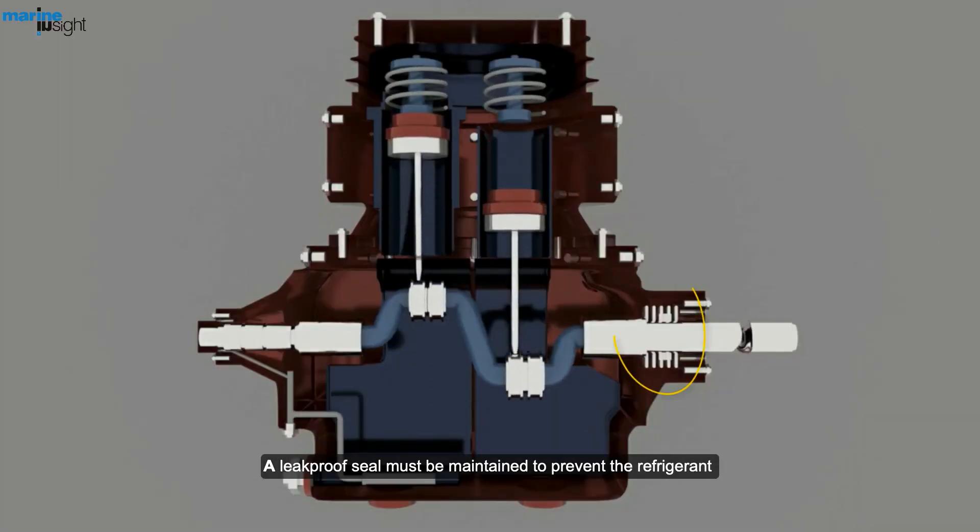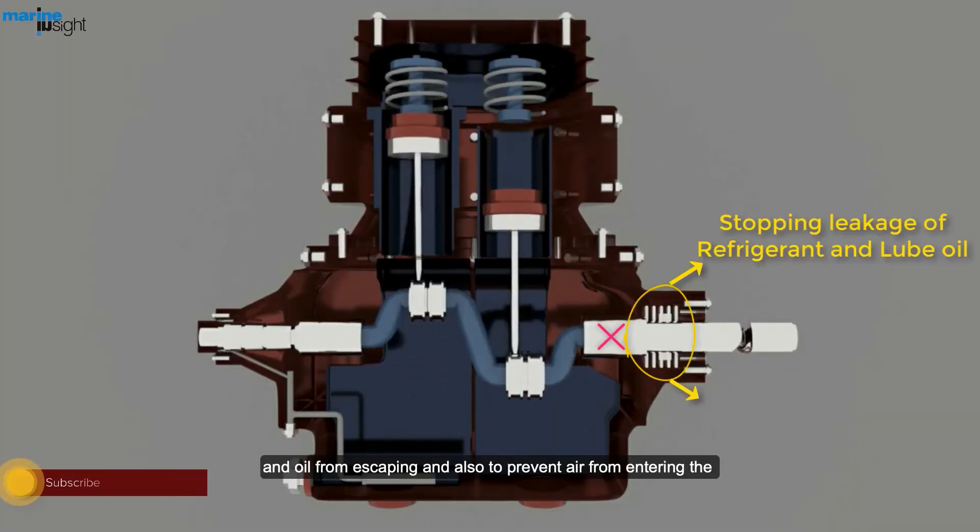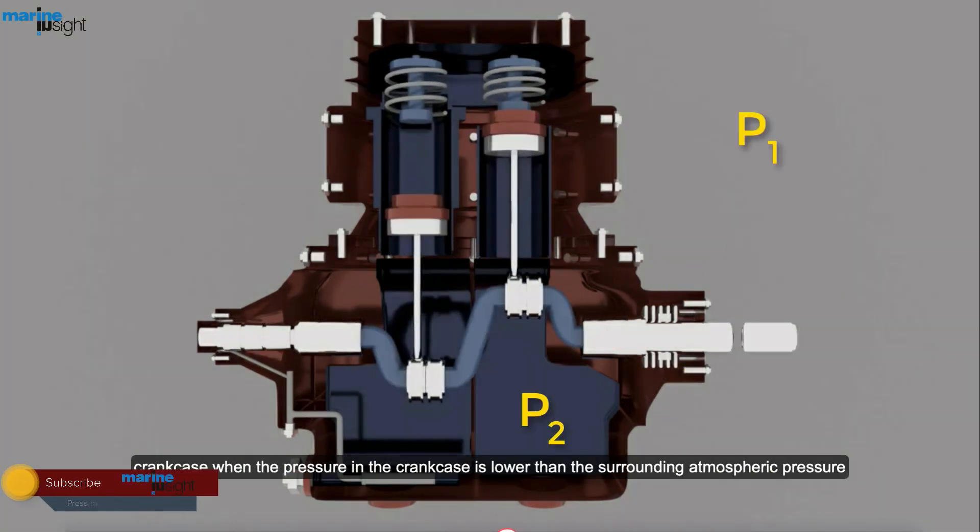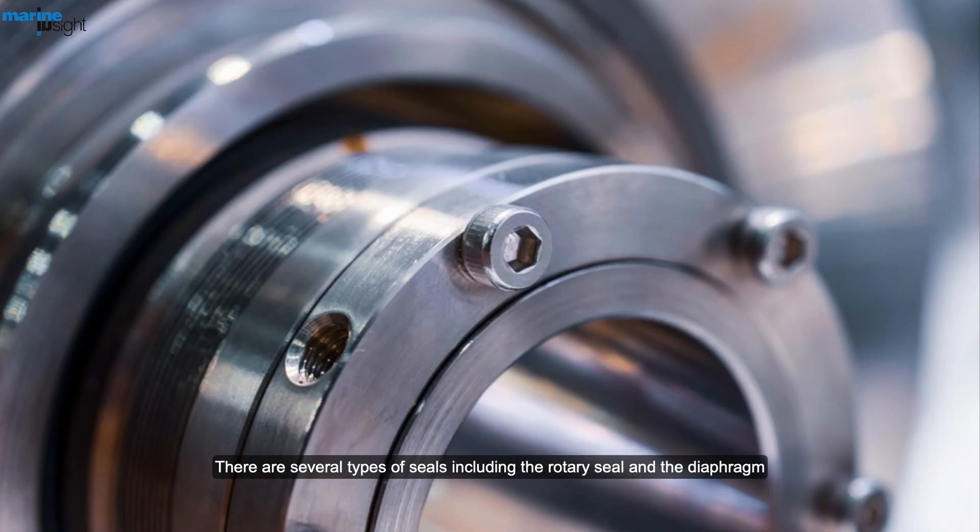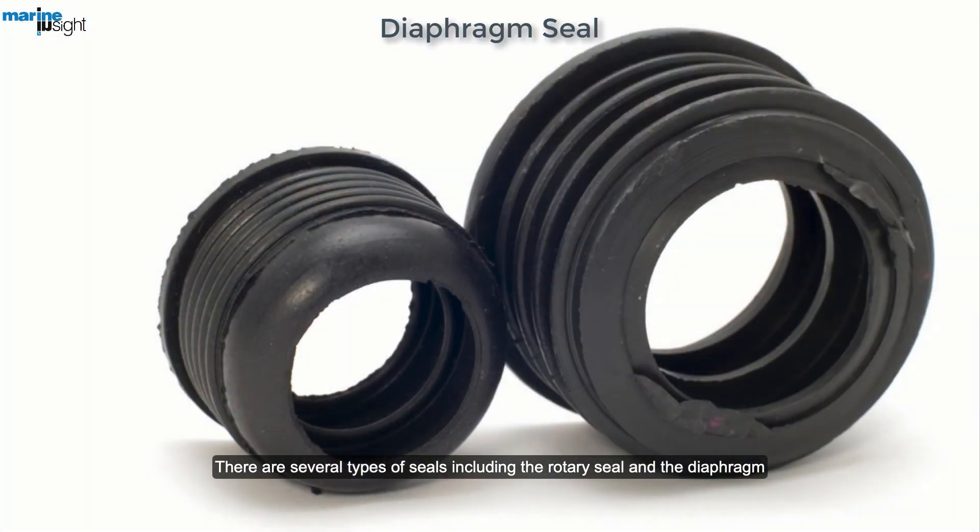A leak-proof seal must be maintained to prevent the refrigerant and oil from escaping and also to prevent air from entering the crankcase when the pressure in the crankcase is lower than the surrounding atmospheric pressure. There are several types of seals, including the rotary seal and the diaphragm.